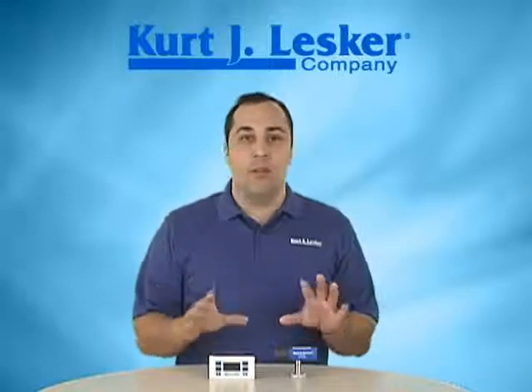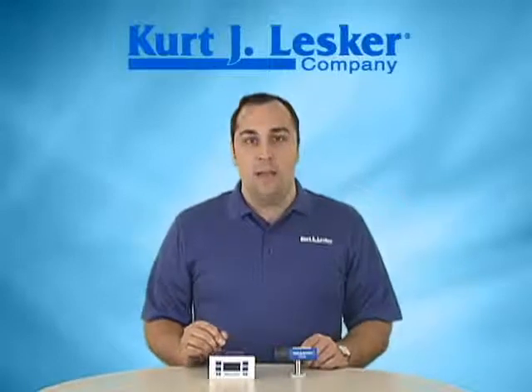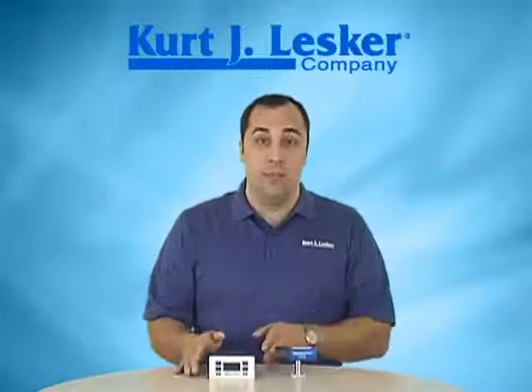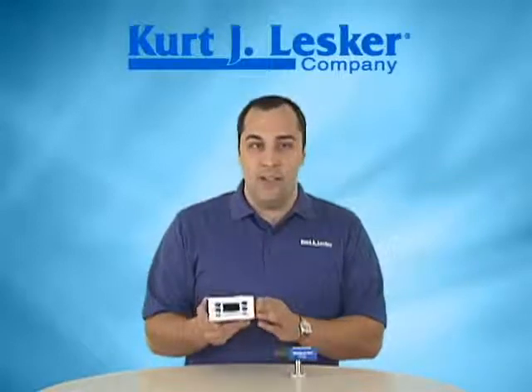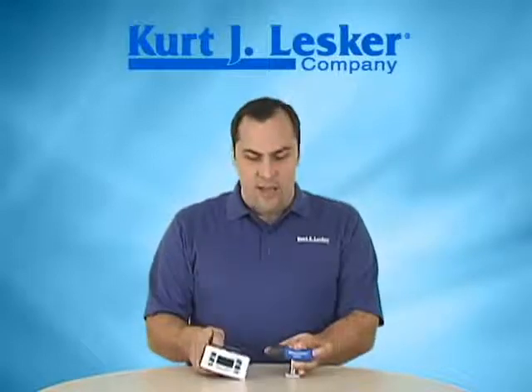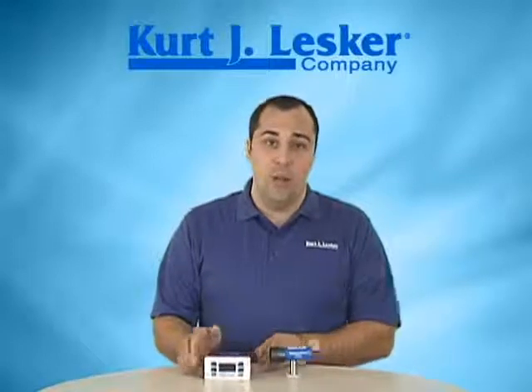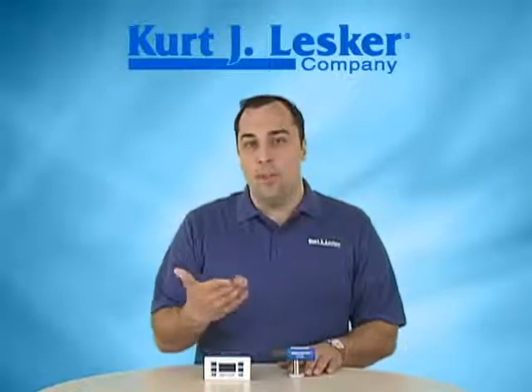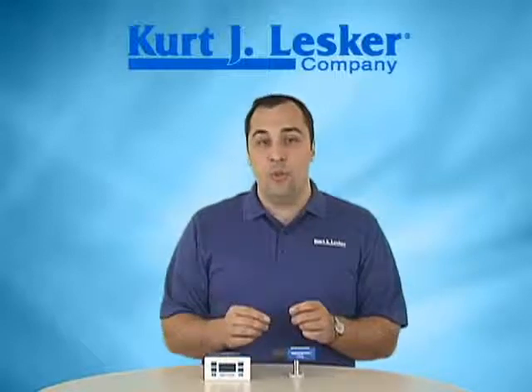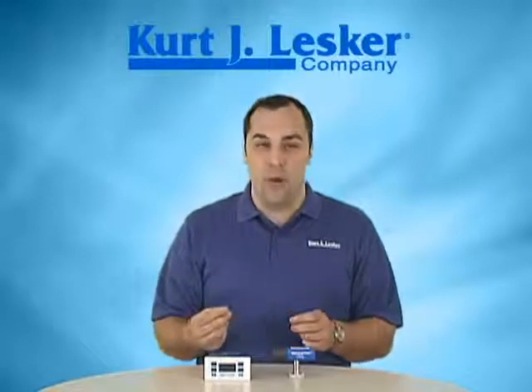I'm responsible for all of our pressure measurement devices. The Lesker Company offers a wide range of gauging options, but this video focuses on our 375 convection gauge controller and 275 convection gauge tubes. Typically just called convection gauges, or Convectron gauges by Granville Phillips, or ConvecTorr gauges by Agilent, formerly Varian, their technical name should really be convection-enhanced Pirani gauges.